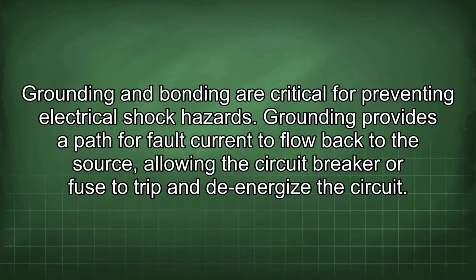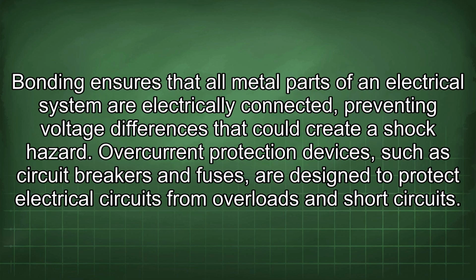Grounding and bonding are critical for preventing electrical shock hazards. Grounding provides a path for fault current to flow back to the source, allowing the circuit breaker or fuse to trip and de-energize the circuit. Bonding ensures that all metal parts of an electrical system are electrically connected, preventing voltage differences that could create a shock hazard. Overcurrent protection devices, such as circuit breakers and fuses, are designed to protect electrical circuits from overloads and short circuits.